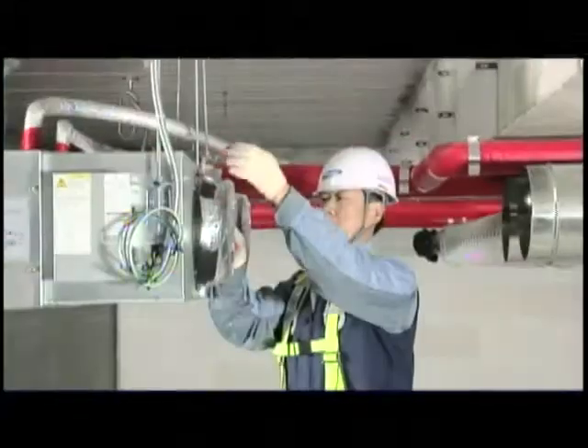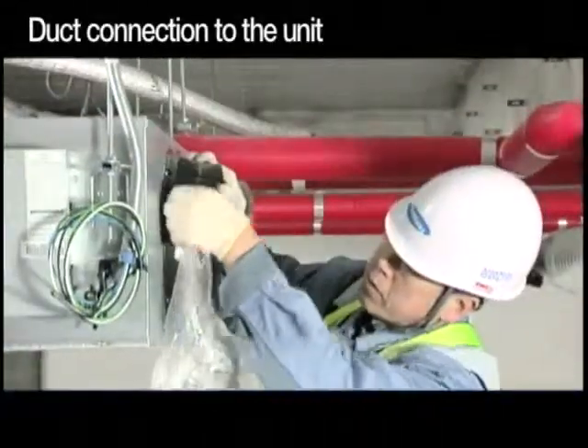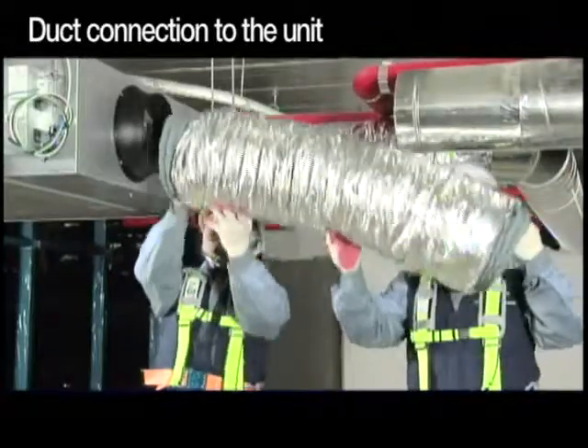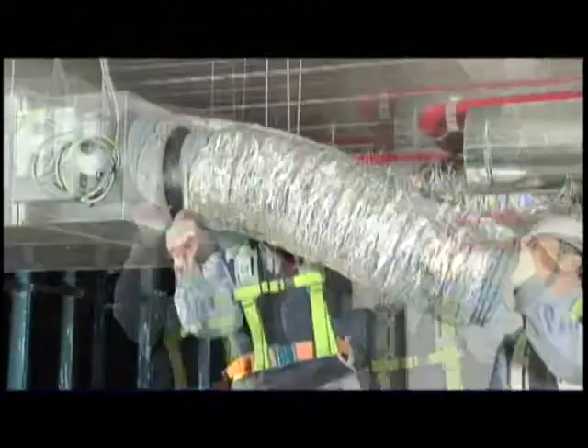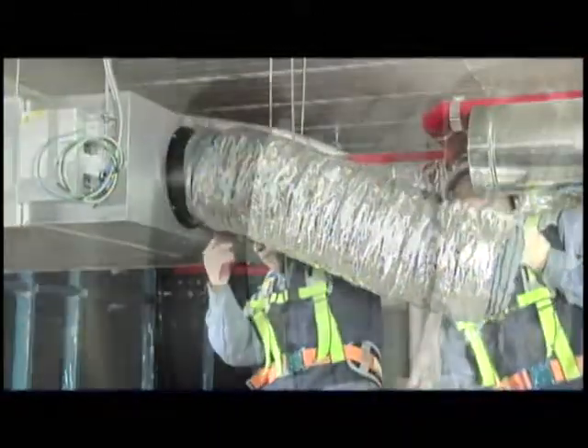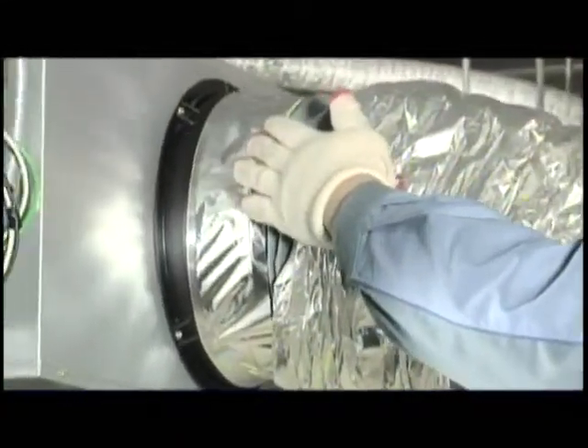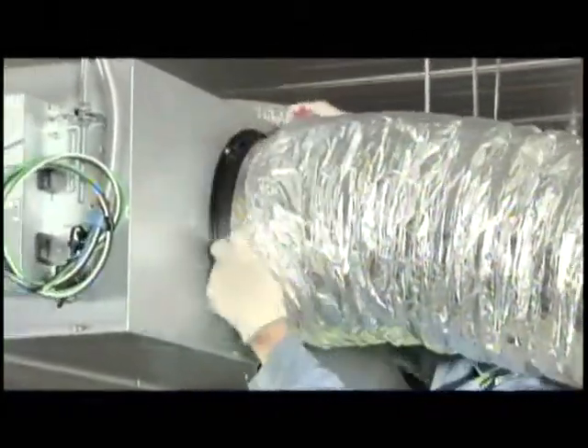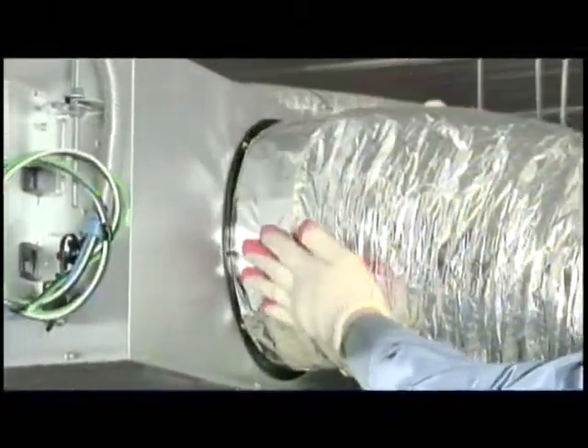To make a connection between the equipment and a duct, first remove the reinforcement materials and connect the ventilation hole and the flexible duct with a clamp and finish it with aluminum tape to prevent air leakage. At this time, to prevent vibration and to absorb noise, a noise-absorbing flexible duct should be used.